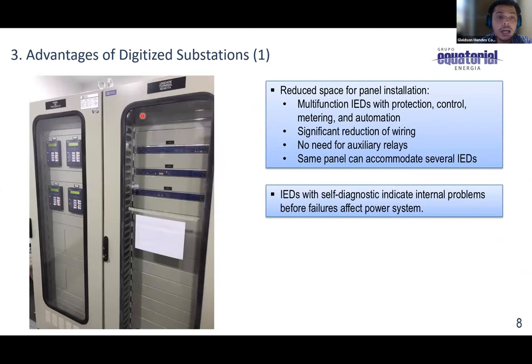Okay. The advantages, the benefits of using digitalized substations are mainly reducing space, using only one panel that can have all the equipment on it. As long as the IEDs are multifunctional, so they have protection, control, metering, and automation, we have a reduction in the usage of equipment on the substation. And all of these functions are integrated on a relay, and this relay occupies a space on the panel.